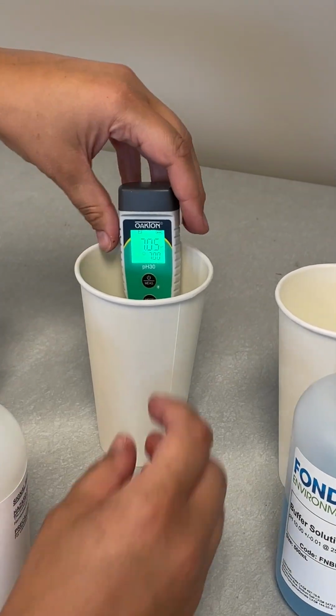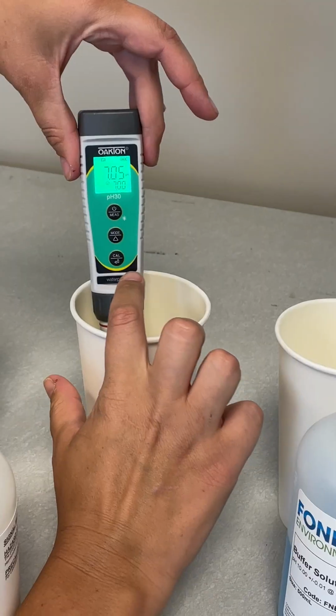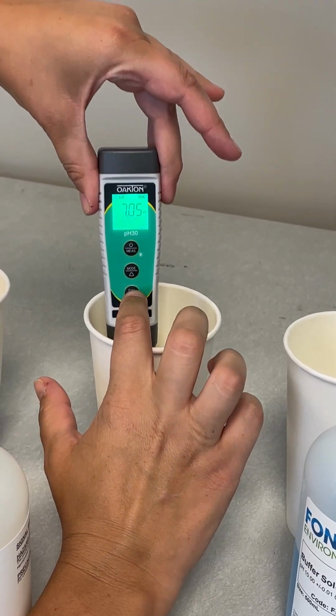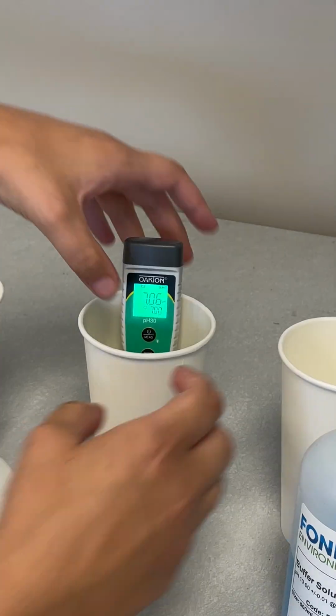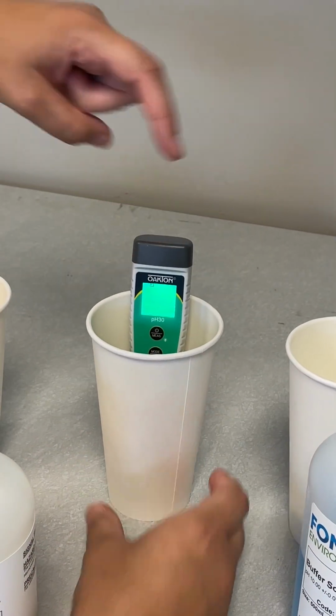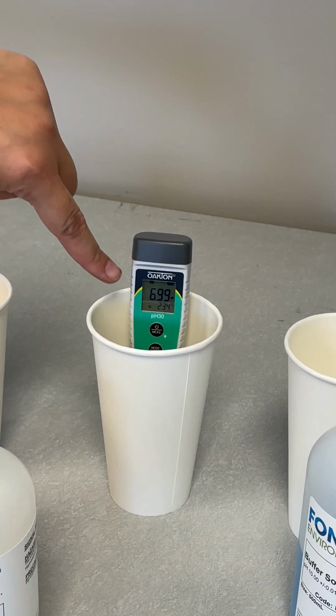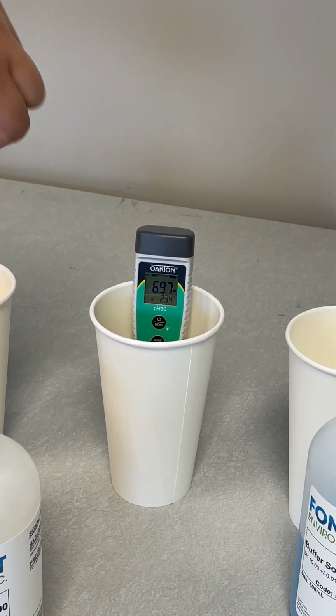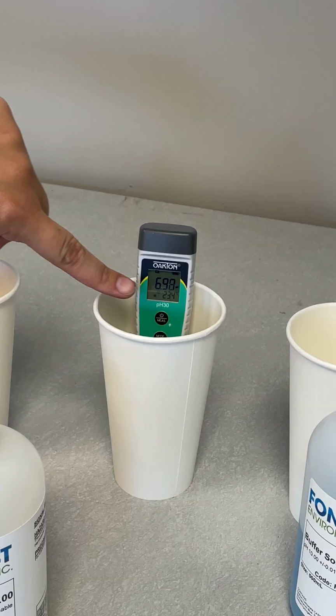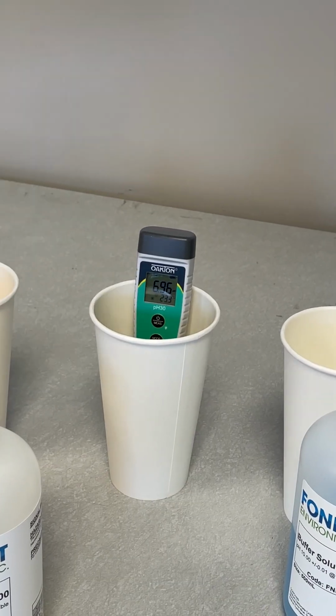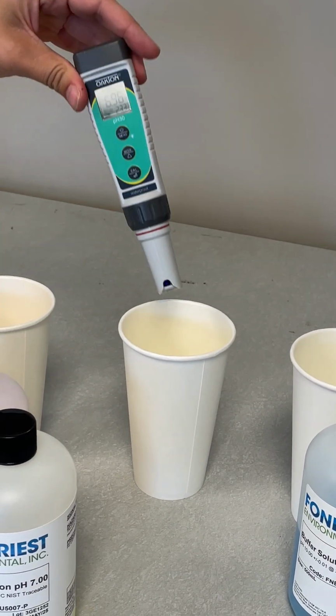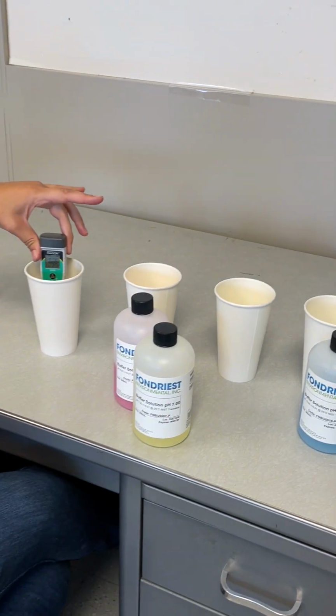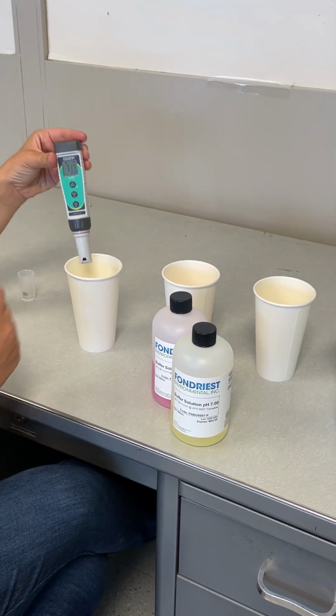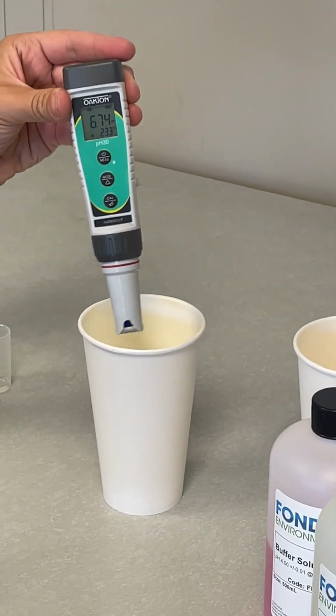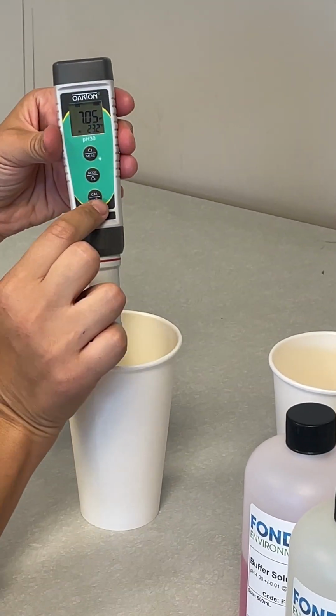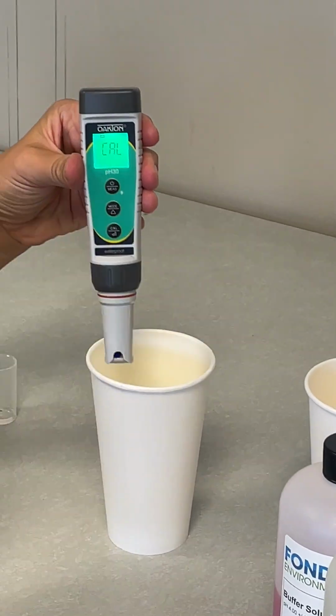And so then this is where I'm gonna short press calibrate. So I'm gonna short press this button, but I'm gonna do it while it's in the solution. You just won't be able to see, so I'm gonna do it. So then it'll blink 7, and when you're recording your pH numbers on the pH sheet, like Form A, you would write down this number. So you'd write 6.96. And then you take it out of the solution, dump it in the water, tap it in the water. You should have a paper towel and dry it. I don't have that.